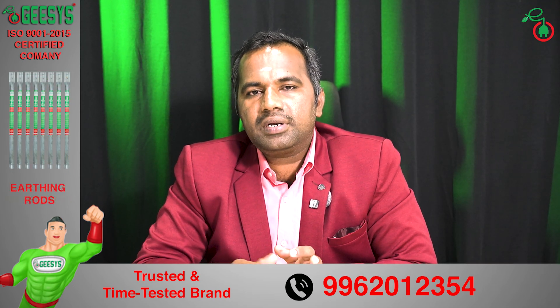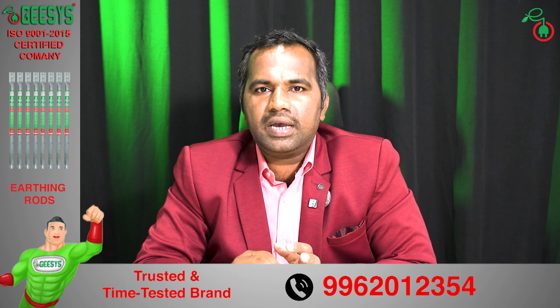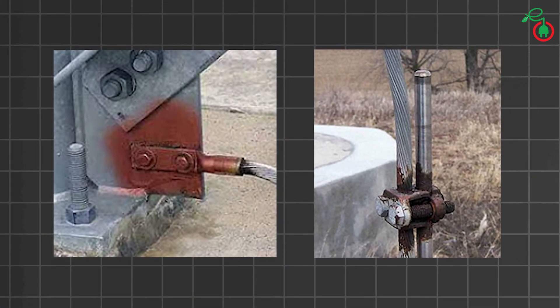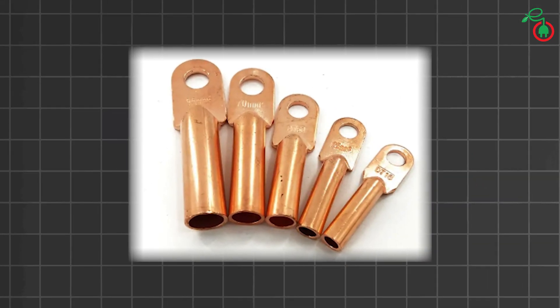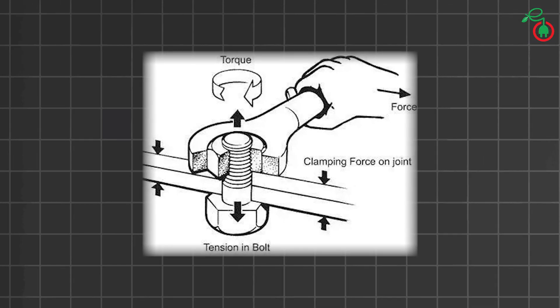For maintaining a proper earthing system at your solar plant, you should have proper testing and verification using an earth resistance tester to verify the resistance value. It is recommended to conduct earth resistance testing on a quarterly basis. Ensure there are no broken or corroded conductors in the earthing system — if you find any, replace or rework them. Use tinned copper terminals for proper earthing and proper crimping of cables, and ensure proper tightness in all parts of the earthing system, checked on a quarterly basis.